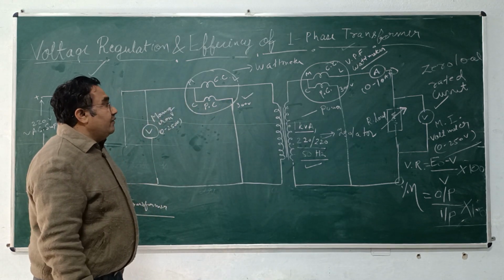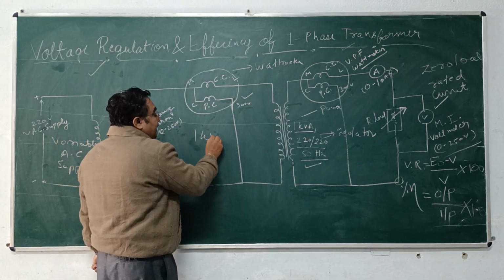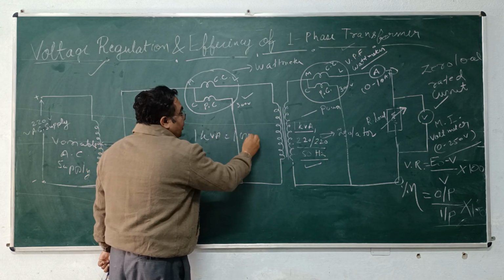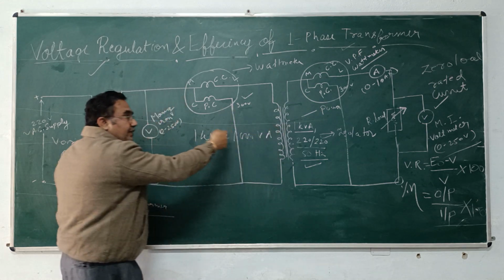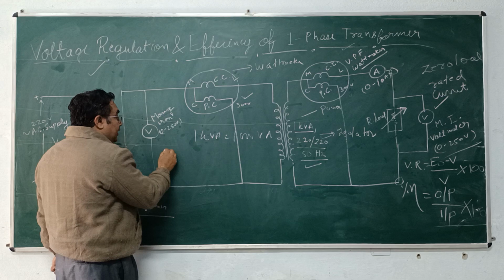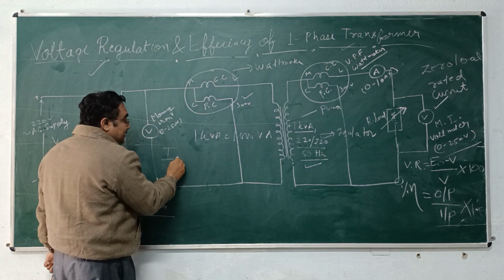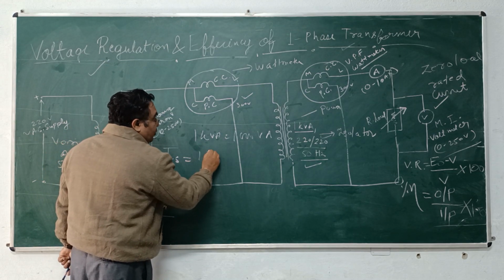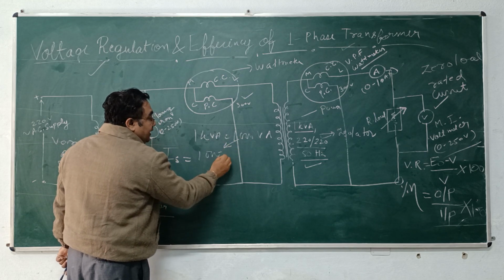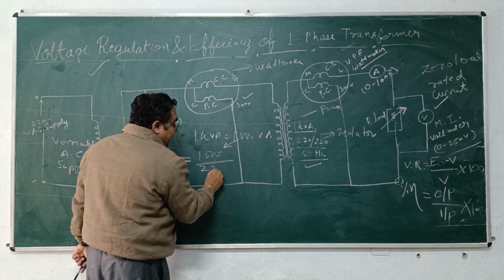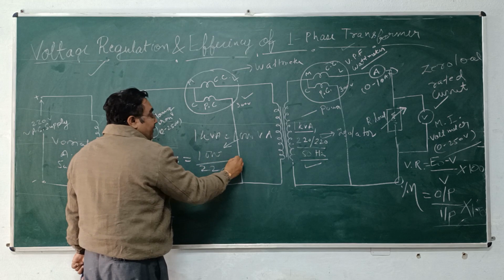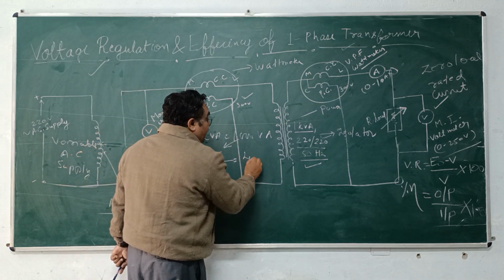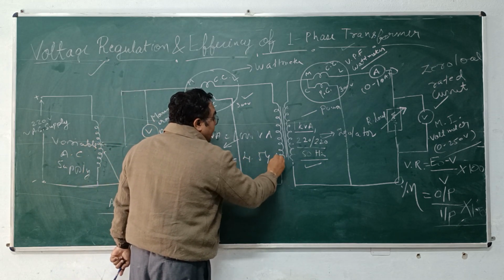What is the power rating of this transformer? This is 1 kVA, which can also be written as 1000 volt ampere. Now with the help of these two data, you can find out the secondary rated current. The secondary rated current will be 1000, that is this reading, divided by the secondary voltage of 220 volt.